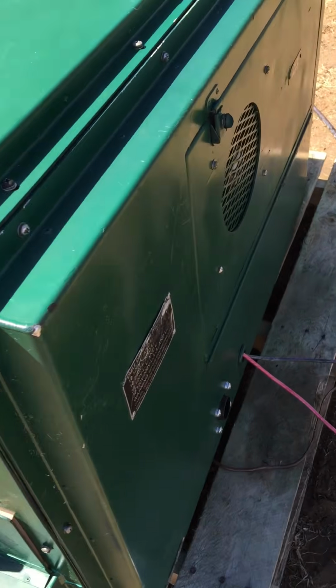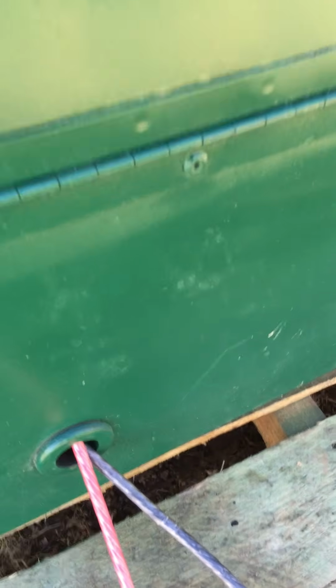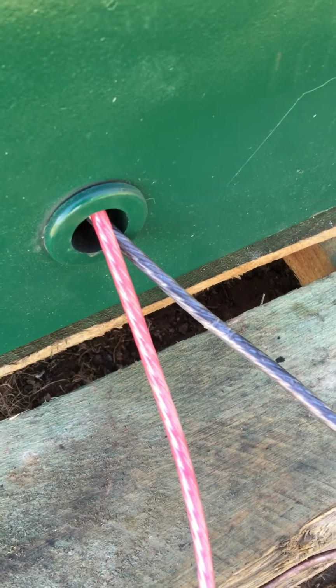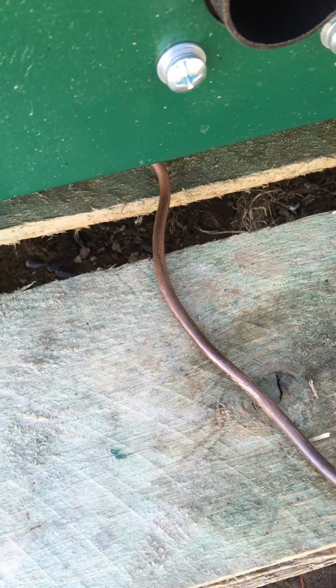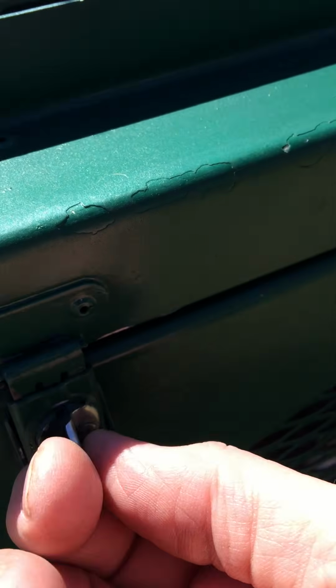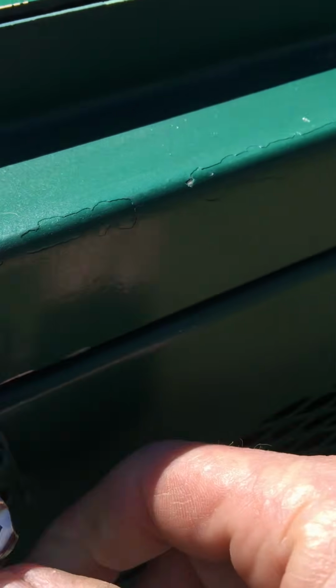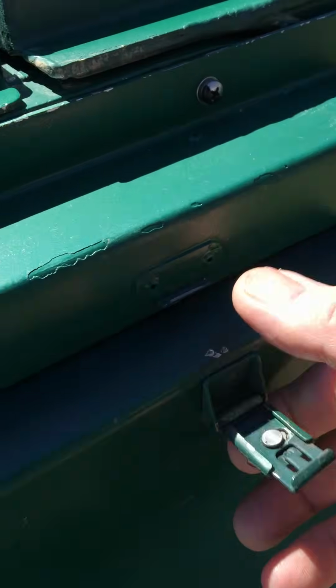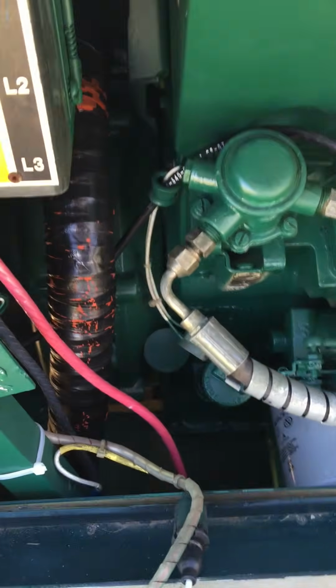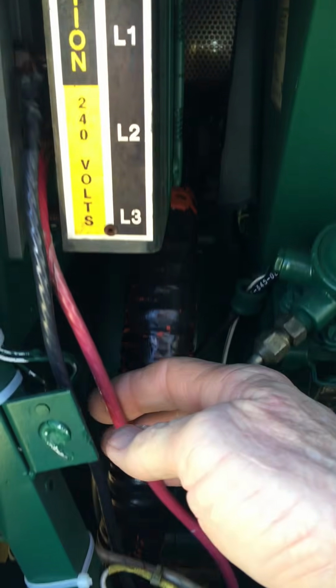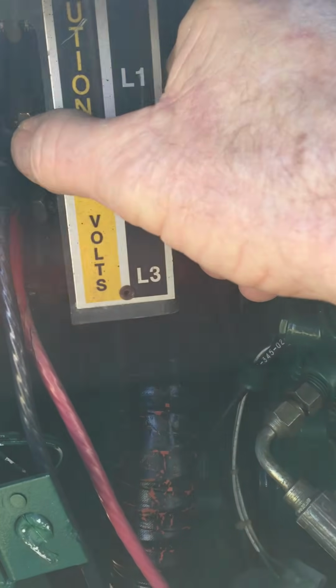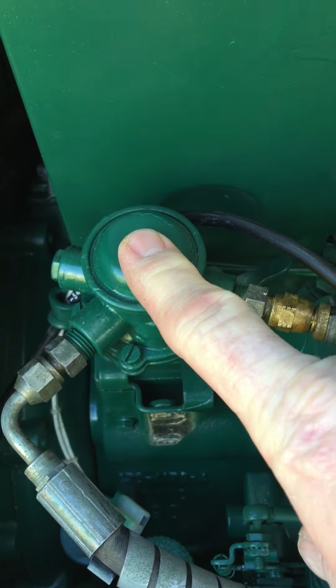We'll move on around the set. Coming down, here are the leads going up to the terminal lugs, and here is a grounding wire. Always make sure that your set is grounded. Come back up. I want to note that on the latch, the handle is missing on this set, as well as over on this side here. We'll fold this door down, and you can see where the leads come up and attach to the terminal lugs with the corresponding phase. Here is the priming pump.